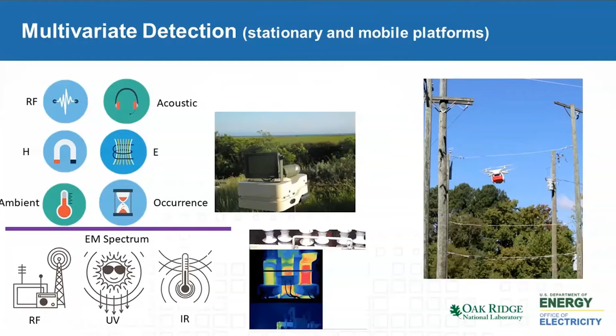Thank you. This thing is rather interesting, and it's the beauty of the software that's layered inside this. And we're not talking really sophisticated things. We don't need a high-performance computer. Heavens, no. But we are having some reasonable computational horsepower doing things. What the graphic is showing is the following. The ultraviolet can pick up arcing, and it looks like that. That's an actual image in UV, looking at some arcing that's happening in that particular substation. What you're seeing it overlaid with is that matrix at 8 by 8. So it's a 64 element matrix that is generated because of radio frequency sensing.